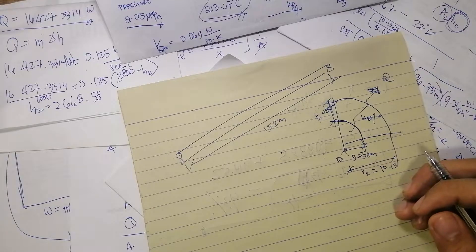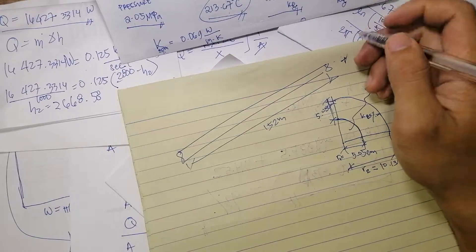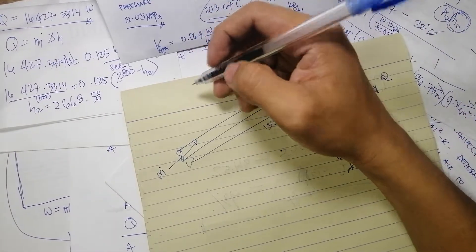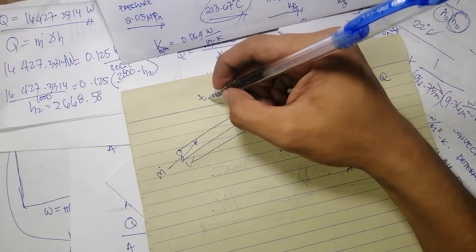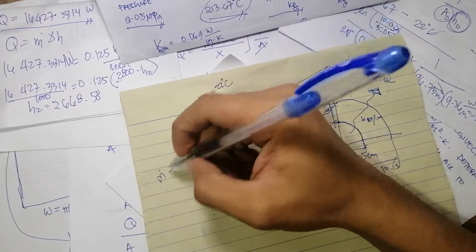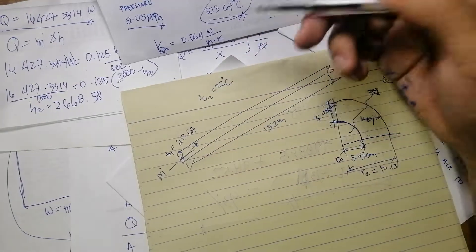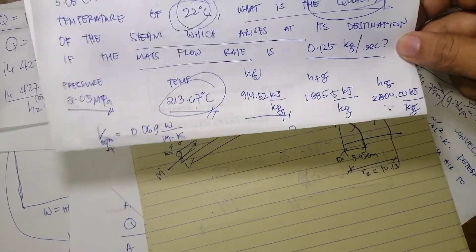So how are we going to solve for the steam, or the quality of the steam which arises at its destination when it goes out here? We have an ambient temperature of air which is 22 degrees centigrade. We have the temperature of the steam passing through, which is equal to 213.67 as per steam table.